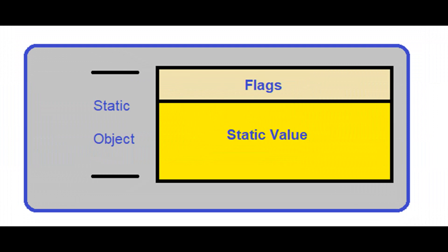DNP3 uses the term static value to refer to an input point's current state or value at the current time; static value and current value are synonymous. DNP3 uses the term static object to refer to a point's static value plus a set of true/false flags that define current characteristics or qualities about each point — for example, whether the point is online or not. Some flags such as online are the same for all input point types; some flags are point-type specific.